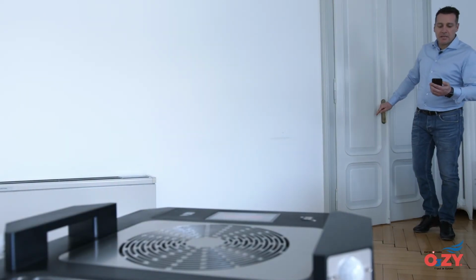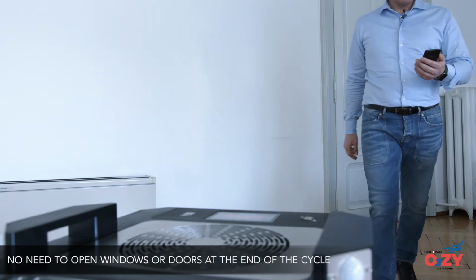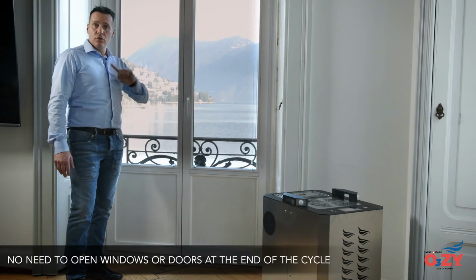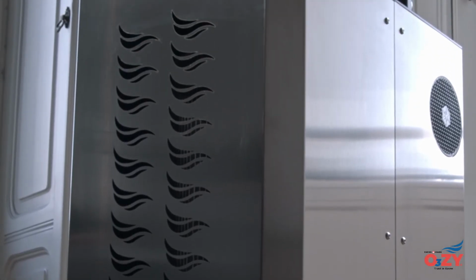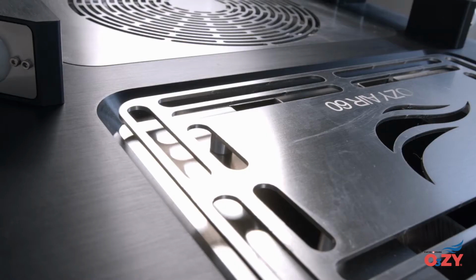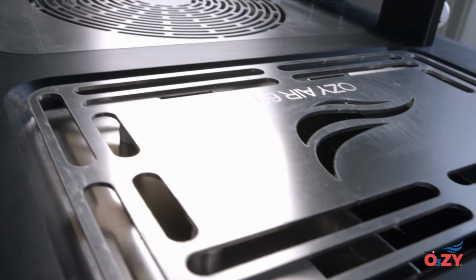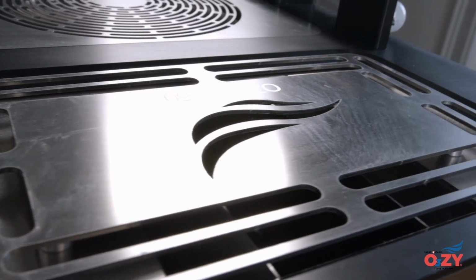The app notified me that the cycle is concluded. Do I need to open the windows? No, with O3ZY it's not necessary. How am I 100% sure it's safe to enter the room again? It's thanks to the sanity filter and the ozone sensor, which reads the ozone value in the room.